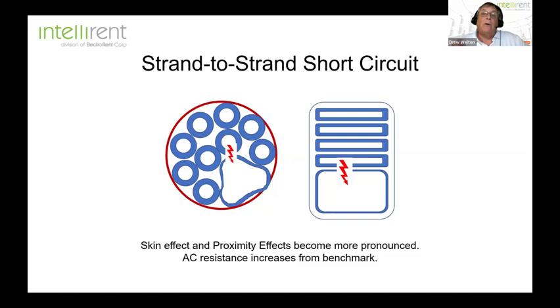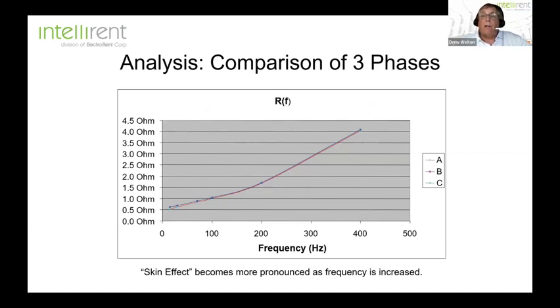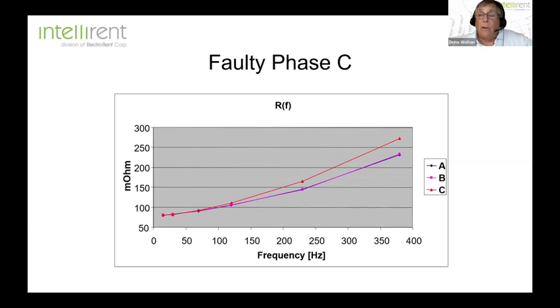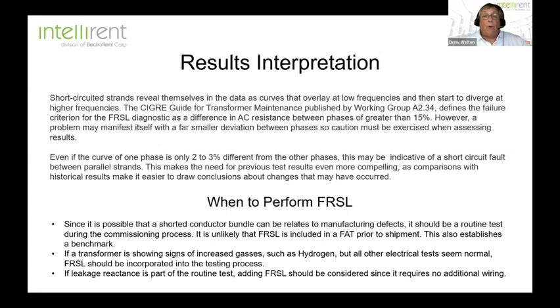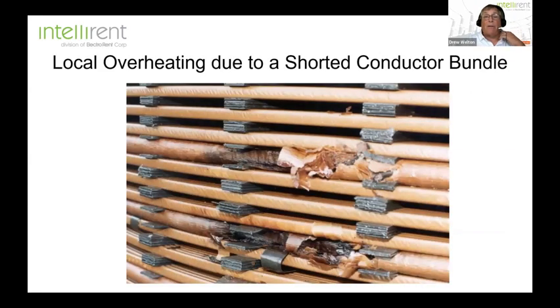It could eventually lead to a hot spot and eventually an electrical failure in the transformer itself. So here's what it looks like normally. All three phases have good symmetry to them. They all follow the same measured resistance from 10 to 50 hertz to 400 hertz. Now we see right here that C phase looks much higher than the other two phases. This is an actual case study. When we tore the transformer apart, this is what happened. This is local overheating due to a shorted conductor bundle.